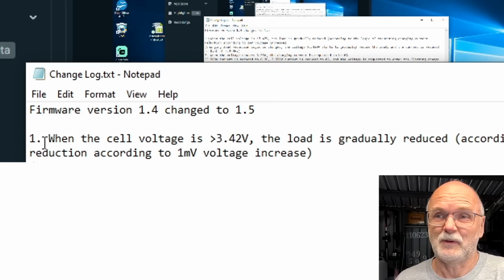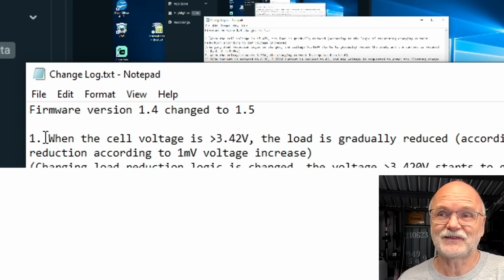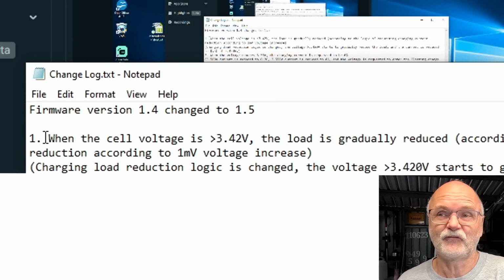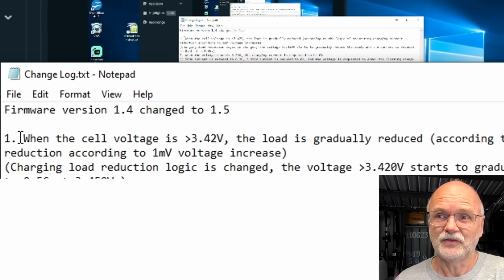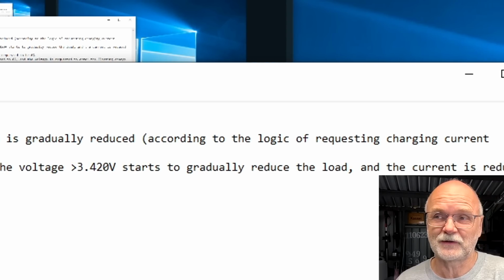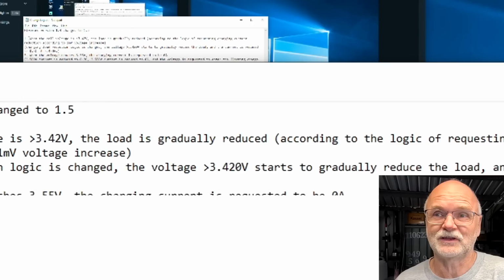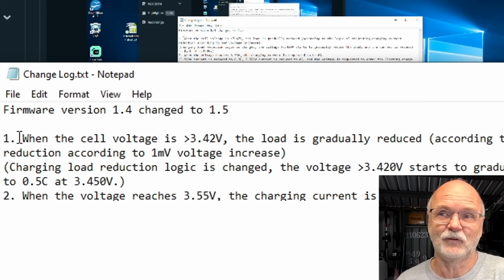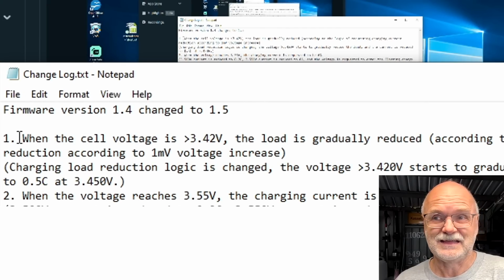Let's have a look. Number 1: when the cell voltage is larger than 3.42 volts, the load is gradually reduced according to the logic of requesting charging current reduction, according to 1 millivolt increase.